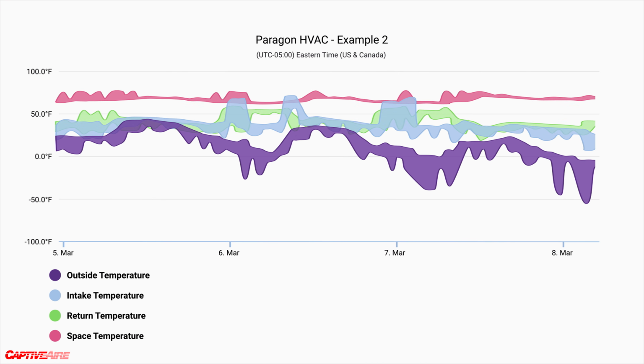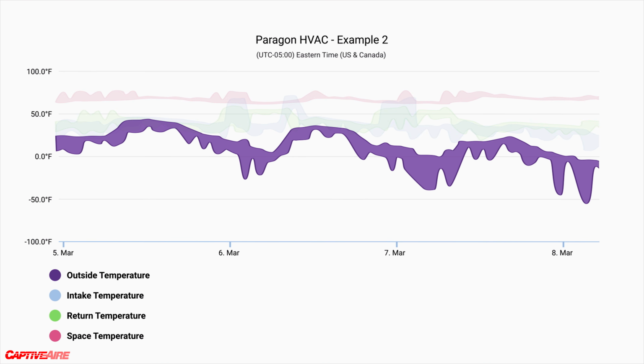So we pulled up the data and found, hey, our temperature readings are not at all where we expect them to be. We know what the outside air weather conditions are, and it was like 50 degrees outside, and our outside air temperature sensor's reading a number that's in the negatives. So this is a clear indication that there's a stray voltage going through our board that's skewing all the temperature readings. All of them are reading off.